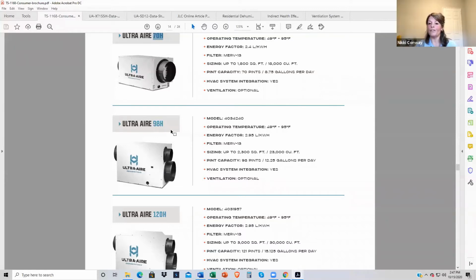If the moisture is too much outside and relative humidity rises in the house due to ventilation and people activities, we'll turn the dehumidifier compressor on and start running it. Now, if we're ventilating at the same time as we're trying to dehumidify the living space, we will remove some moisture from that air. But the reality is you need exposure time to remove moisture, and one pass over the coils really isn't going to remove that much.